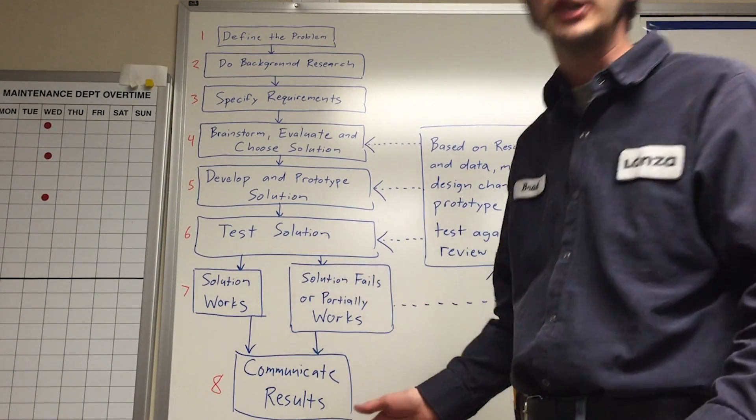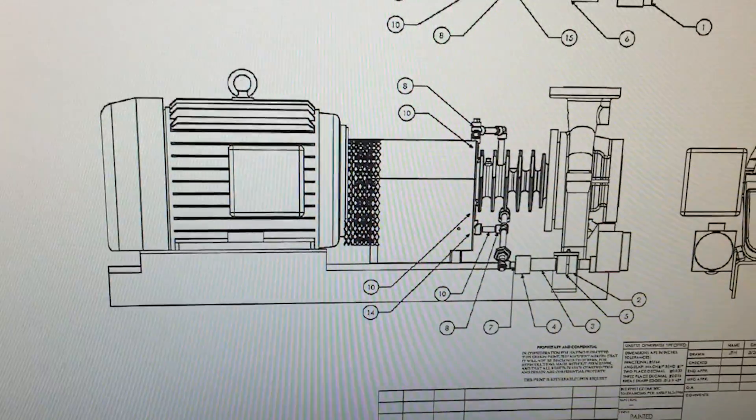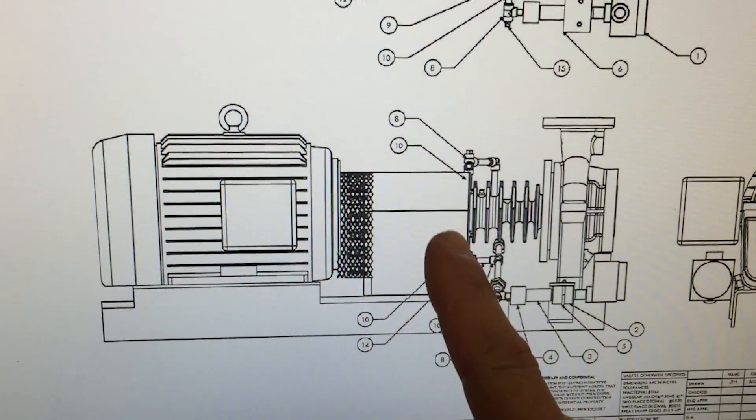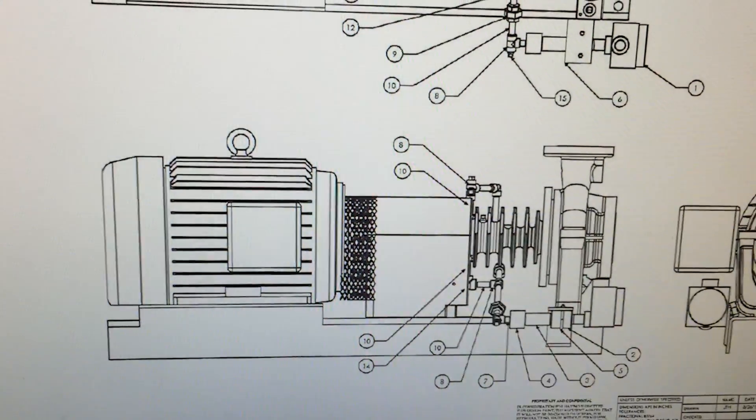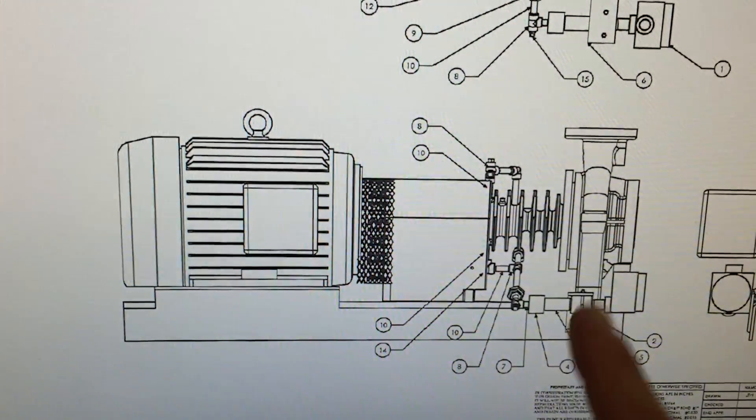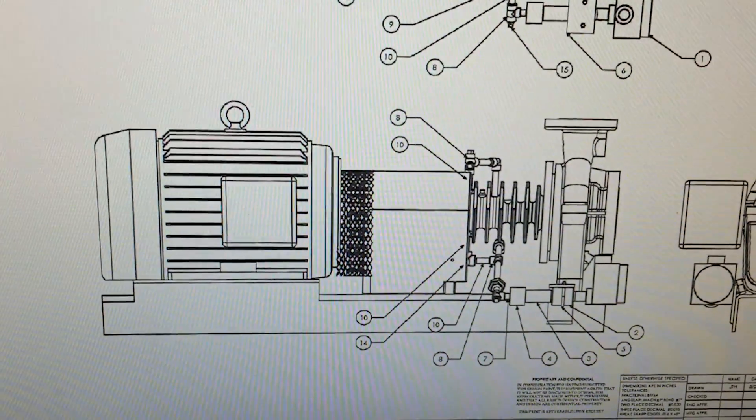So that's the general basis and general flowchart for problem solving I use. Now let's take a look at an actual example. Here's our example problem. We have these particular pumps and we put these leak detection systems on the pump mechanical seal housing. Mechanical seal being the device that holds the process fluid into the pump as it operates. We never had issues before, but ever since we put these in, the seals leaked all the time, which is rather unusual.